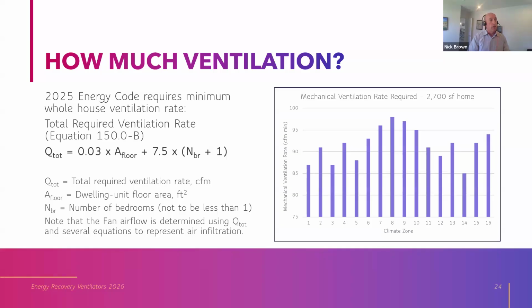And the energy code, as I said, adopted the ASHRAE 62.2 standard. That's how it calculates the minimum airflow rate based on the conditioned floor area and the number of bedrooms. It calculates a total required ventilation rate. There's actually another step where it calculates an infiltration rate, and then it subtracts the infiltration rate from this total calculation, and that gets you the fan airflow rate that's required.